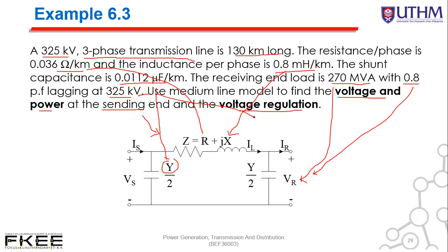So we use the equivalent circuit. Given the value at load is 270 MVA, 325 kV, 0.8 lagging. And also given the distance of 130 km, R is 0.036 ohm per kilometer, inductance 0.8 millihenry per kilometer, and also capacitance of 0.0112 microfarad per kilometer. So we can calculate the series impedance per phase, Z equal to R plus jX. So just replace the values of R, L and C given.